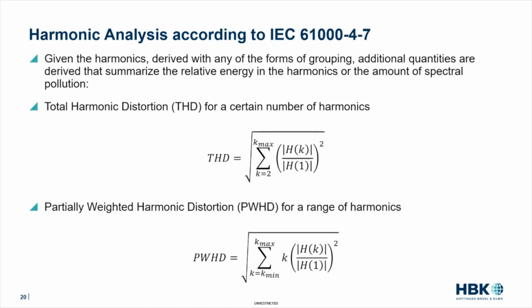The standard also prescribes quantities that can be seen as a summary of the total harmonic content or the total harmonic pollution. Given the harmonics derived with any form of grouping, those additional quantities are defined as follows. I think the first one is very well known. That is the total harmonic distortion, which is the ratio of the energy in all the harmonics except the fundamental divided by the fundamental. The standard allows you to put an upper limit, in this case K max, on the number of harmonics you want to take into account. The second one is the partially weighted harmonic distortion, the PWHD, which is similar but in a slightly different form. The higher harmonics are weighted more heavily in the total summary.